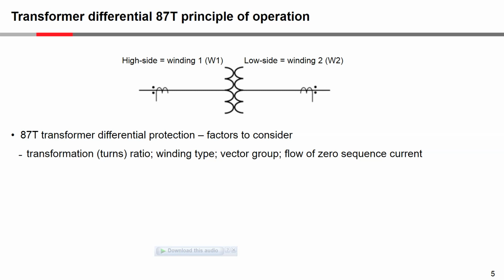We're talking about vector group, and this is really what gives the phase difference between the currents coming in on the one side and the currents exiting on the other side, and whether zero sequence current can flow in the measurement circuit on the one side where it cannot flow on the other.